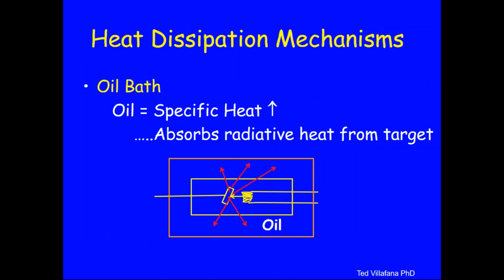So, tube warm up. Here's another heat dissipation mechanism. By the way, on the tube warm up, I've noticed these days we buy tubes that have relatively high heat capacities, so you don't see techs warming up tubes very often. The only times they would warm it up very often is if they happen to have tubes that have very small focal spots. Small focal spots mean that the heat load is concentrated in an even smaller spot, so you're more at risk for building up to the point where you have a meltdown.